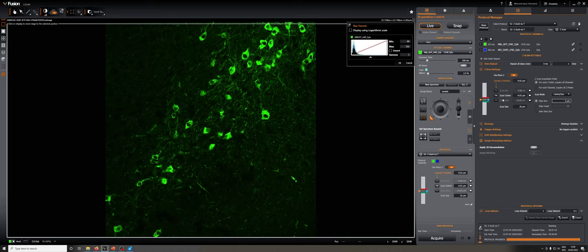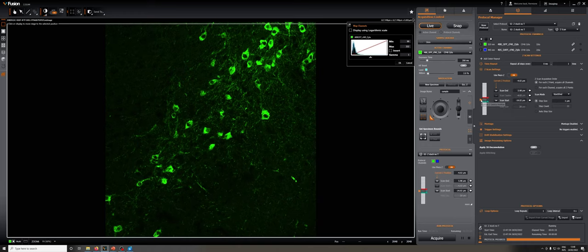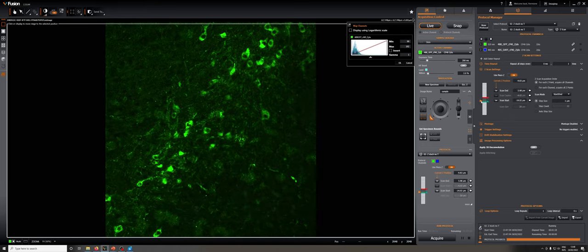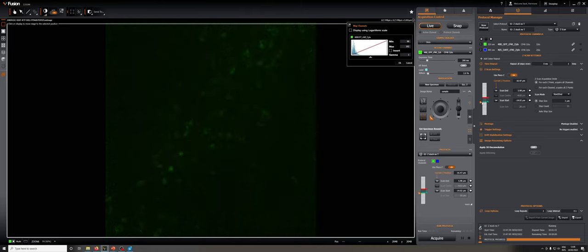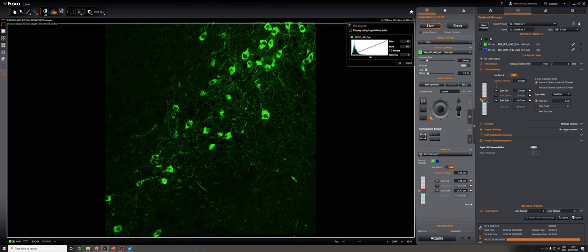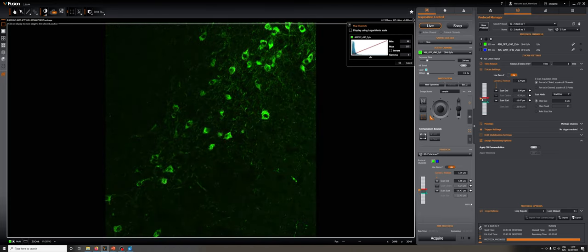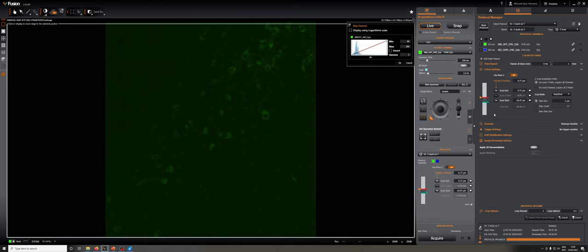That's one option for how we take this. The other option is to set the start and the end. In that case, we move the piezo down to the very bottom, set that there, that's where we're going to start. And we go to the top, set that there, that's where we're going to end. When we're in this mode, we can also just move the start and end sliders, which are these green and red ones respectively, to mark the edges.